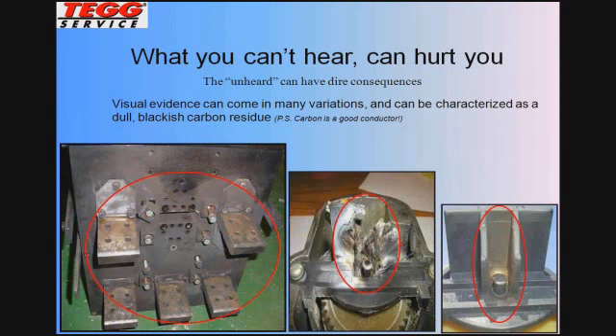The visual evidence that I mentioned related to the tracking anomaly comes in the form of carbon. And I have 3 images here that show the byproduct of tracking occurring. On the left-hand side was a 3,000 amp bolt-in circuit breaker sent to us by one of our customers. They identified this issue and were able to isolate it down to the line side of the B phase on the breaker as the highest intensity level.